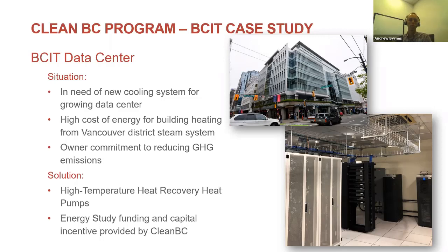The solution we came up with was using heat pumps to provide cooling to the data center, producing chilled water for that purpose, as well as high temperature hot water for heating the building, which ties into the existing building hydronic heating loop. We had to use high temperature heat pumps due to the original design of the building, which uses heating water up to 180 degrees Fahrenheit—fairly hot and not something most heat pumps can produce. But we found an innovative way to tie into the high temperature building heating system using a high temperature heat pump.